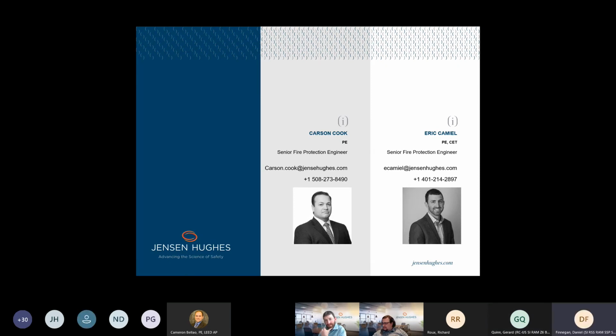Yes, good afternoon, gentlemen. Eric, Carson, job very well done. I had one question, and it revolves on the fact that you did a great job of focusing in on the 2-hour rated pathway or the 2-hour rated shaft closet arrangements. What do you feel when you come across one of those and it's got the rated room as far as construction, it's got a UL rated frame and door on it, but because the door is always kept locked because of its electrical room nature, there is no door closer on it. Are you still accepting that as a 2-hour rated assembly?